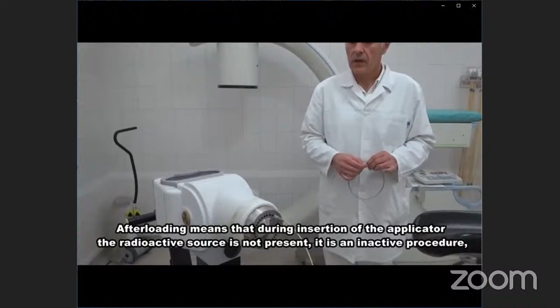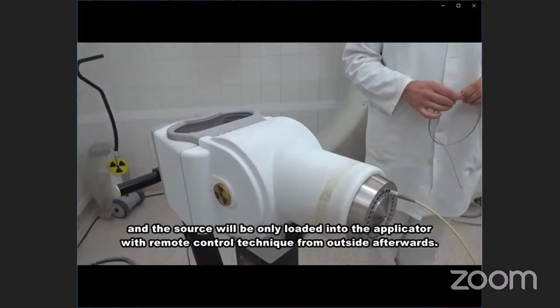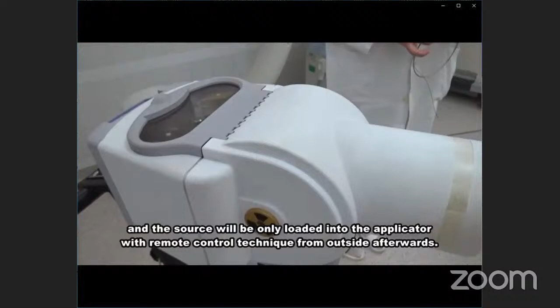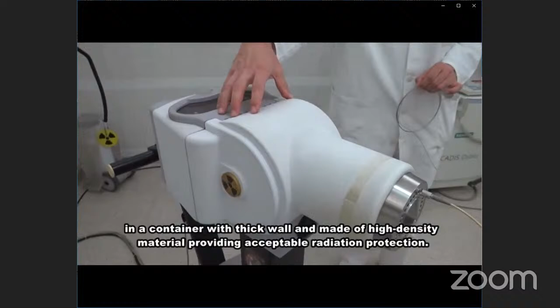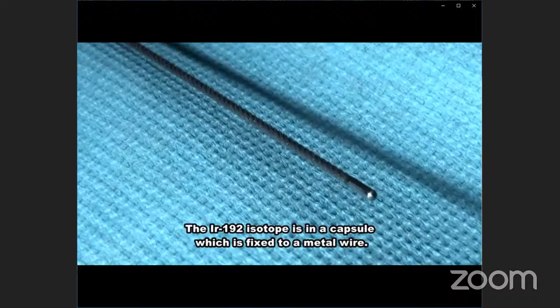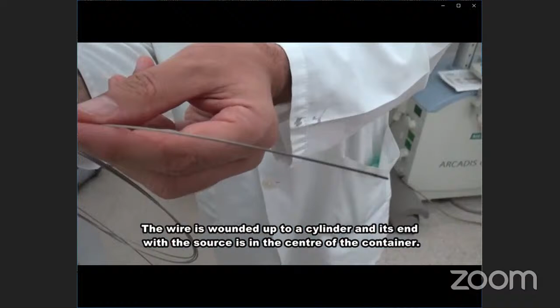High dose rate afterloading means that during insertion of the applicator, the radioactive source is not present. It is an inactive procedure, and the source will be only loaded into the applicator with remote control technique from outside afterwards. Currently, the radioactive source is in the head of the machine. Here, in the center, there is a container with a thick wall and made of high-density material. And this is how the source looks like. The iridium-192 isotope is in a capsule, which is fixed to a metal wire. The wire is wound up to a cylinder, and its end with the source is in the center of the container.